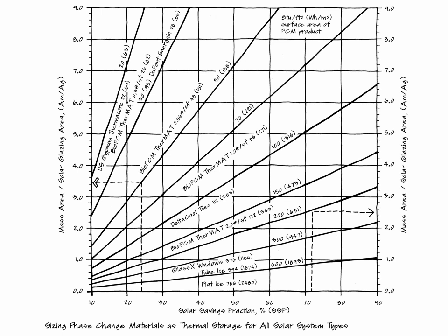Now, for phase change materials, there's a lot of stuff out there on the market. You have to go to the manufacturer. You have to look at the specific product that you're interested in. For instance, Delta Cool tiles, that gives a value on the chart here of 112. There's no line for that, but you can see the line for 100. So we've just put in some examples of the kind of BTUs per square foot of material that's exposed of that product. So Delta Cool tiles is a phase change material that's built into a ceiling tile. You have a drop-in ceiling, and you can use that for thermal storage, right?